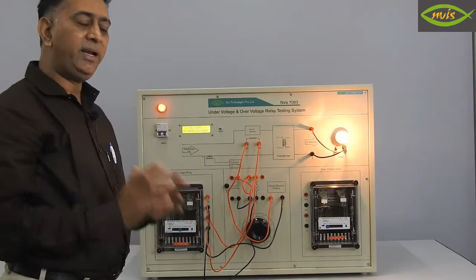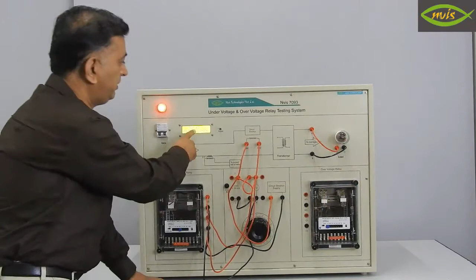So now I am moving this in the anti-clockwise position again, in reverse: 96 volt, 95 volt, 91 volt, 88, 86, 80 volt, 78 volt. Our plunger is set at around 65 volt: 70, 69, 67. Yes. So at 65, immediately this relay is tripped off. So this is the perfect working of the relay we have seen here.